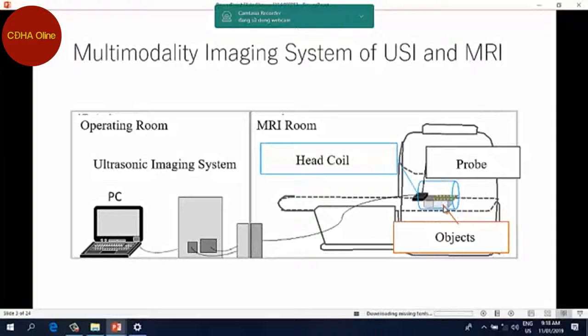In this case, it is important to suppress the electrical noise. So we use this double input connector here. This is the wall dividing the MRI room and the operating room. The probe is connected by this connector, and the ultrasound equipment is connected by this type of connector. So we can ground the line here, and we can suppress the electrical signal. This is, as I just explained, the operating room and the MRI room, and the probe here.